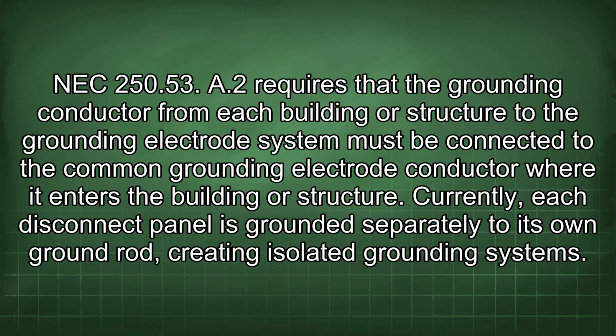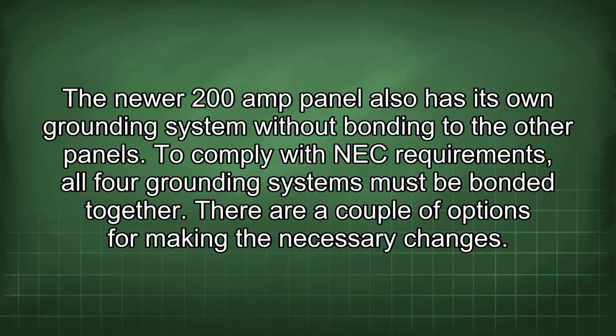NEC 250.53 A2 requires that the grounding conductor from each building or structure to the grounding electrode system must be connected to the common grounding electrode conductor where it enters the building or structure. Currently, each disconnect panel is grounded separately to its own ground rod, creating isolated grounding systems. The newer 200 amp panel also has its own grounding system without bonding to the other panels.